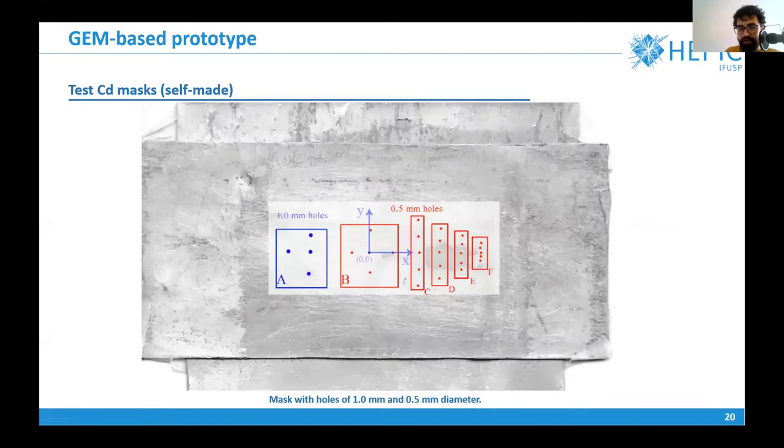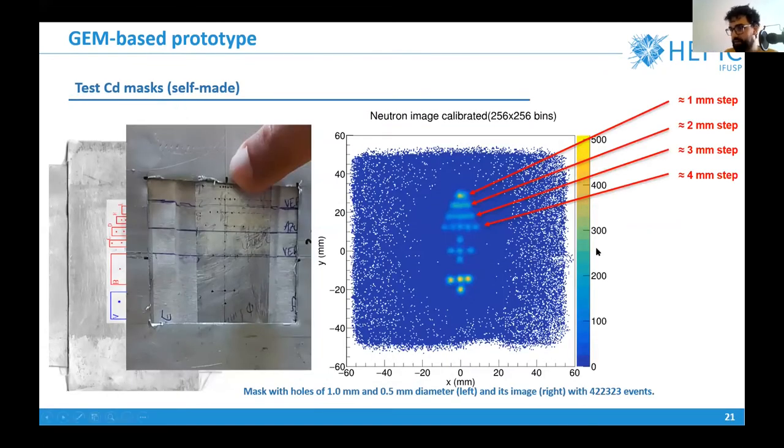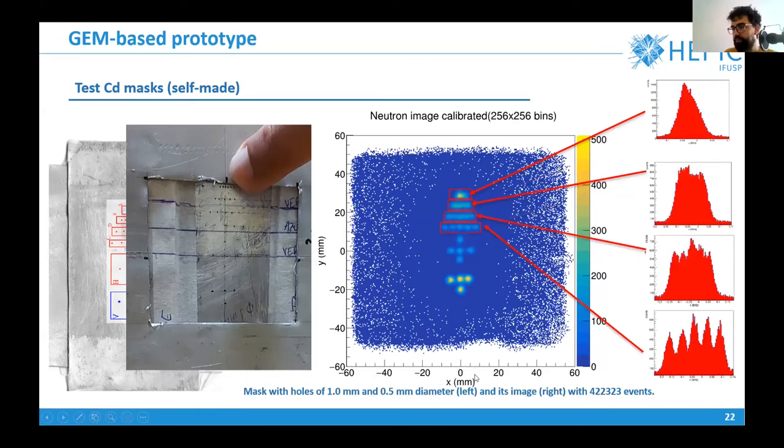We tried different shapes and disposals of these holes. With these different disposals here we have half millimeter holes. In these lines we have these half millimeter holes with different steps between each other. Here we have four millimeter steps and so on. If we plot the X profile of these steps, we can see that at some point we cannot distinguish anymore between the holes. So it gives us an idea about the spatial resolution of our detector.